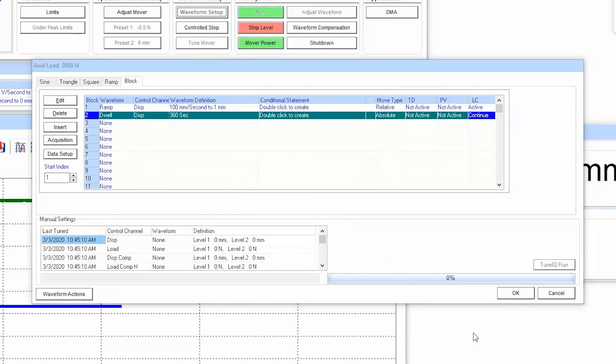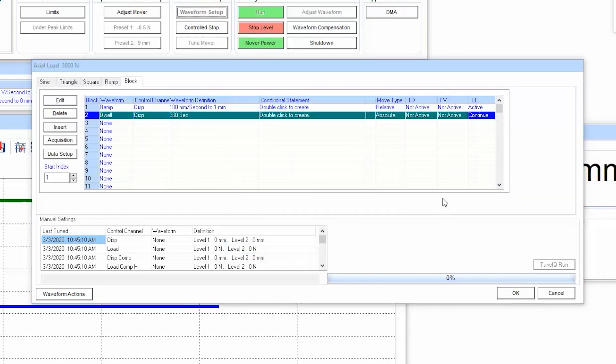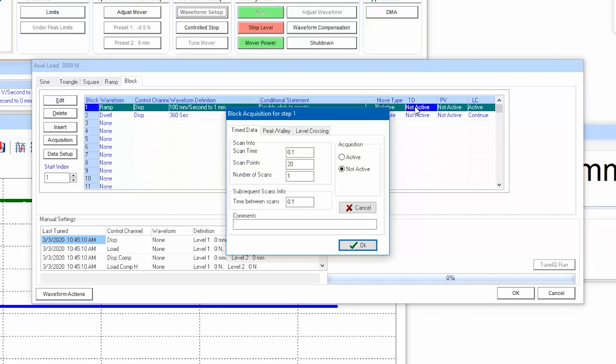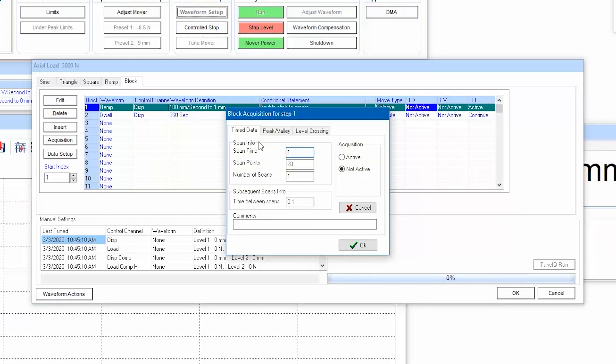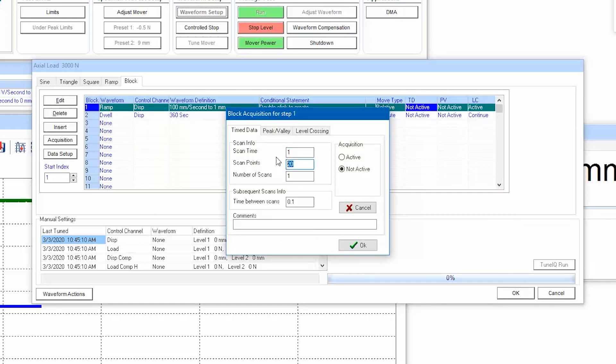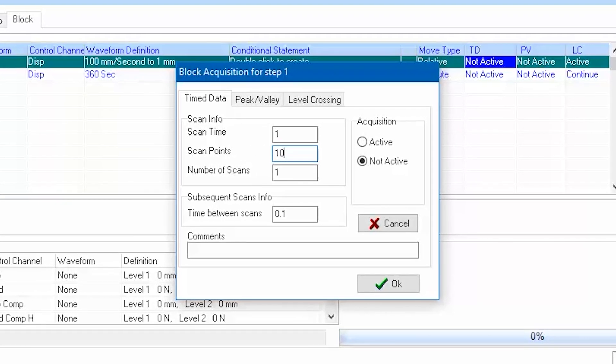Notice that if you're running a block test protocol, you can also define time data and peak and valley data to each block step. For each row, double click on the data type desired and fill in the desired data settings. One useful tip is to set a one second long scan time so that the number of points per scan equates to the sampling rate. An artificially long number of scans can be entered knowing that the data acquisition will jump to the next row upon completion of each block step.